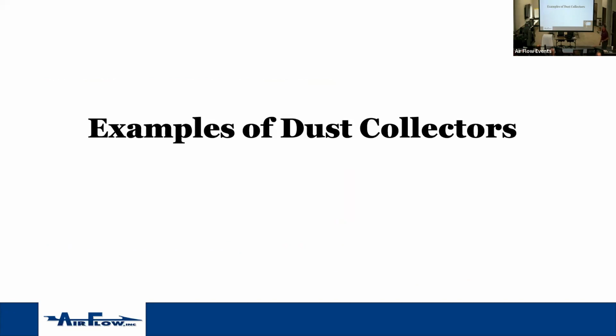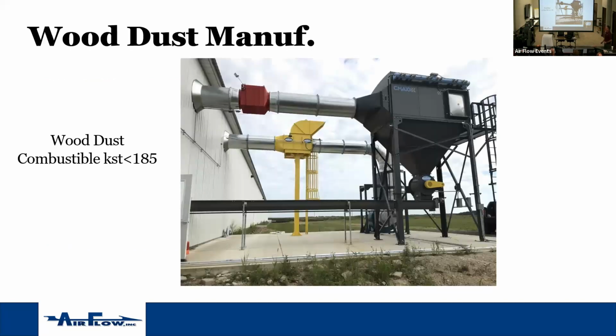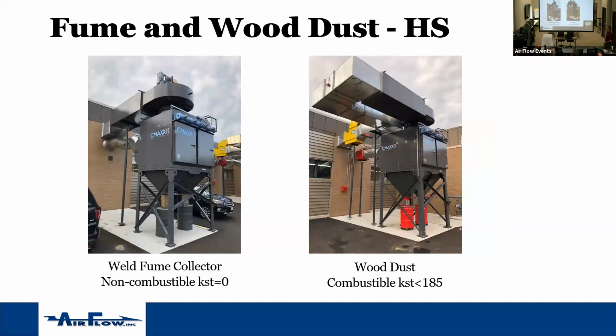A couple pictures to close out here of some dust collectors. This is a great picture, it shows everything. Here's a wood dust Kst less than 185. There's your explosion panel up high enough, directed away from the building. Your dirty air coming in, your EIV with the set distance from here to the collector, your abort gate on the clean air side, and your rotary airlock. Everything's protected. So a couple of these, this is also a wood dust system. All the safeties are in place.